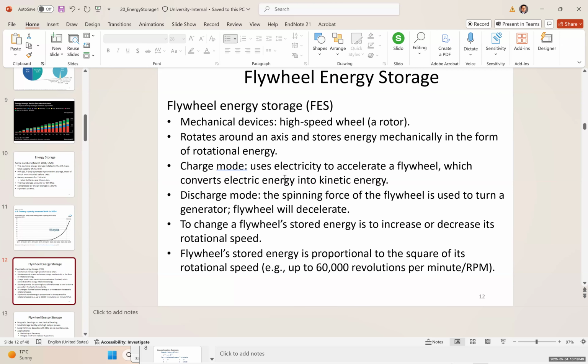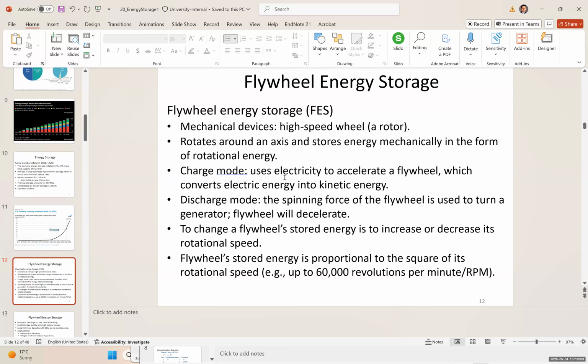Now let's talk about different technologies of stored energy systems. The flywheel energy storage is a mechanical device—a high-speed wheel, or rotor, rotates around an axis and stores energy mechanically as rotational energy. In charge mode, it uses electricity to accelerate the flywheel, converting electrical energy into kinetic energy. In discharge mode, the spinning force of the flywheel turns a generator and the flywheel decelerates. Usually the motor and generator are the same single unit: it acts like a motor when given electrical energy, and when power is cut, the flywheel turns the motor, which acts like a generator.